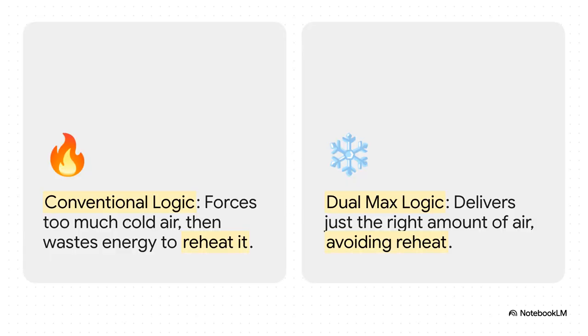And this is where the absurd energy waste happens. With the old logic, that oversized box dumps way too much cold air into a room. The room gets too cold, so what does the system do? It kicks on a reheat coil, basically an electric heater, to warm up the air it just spent a ton of money cooling down. It's exactly like driving your car with one foot on the gas and the other on the brake. It's insane.